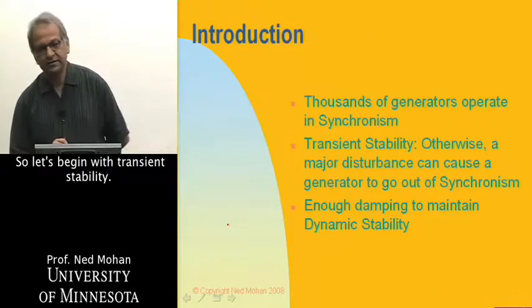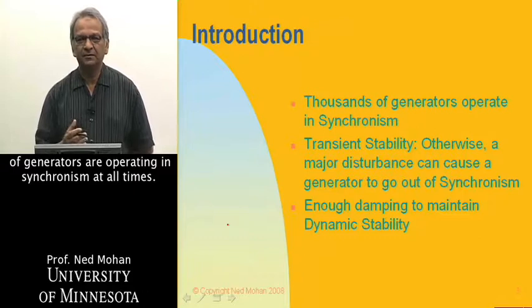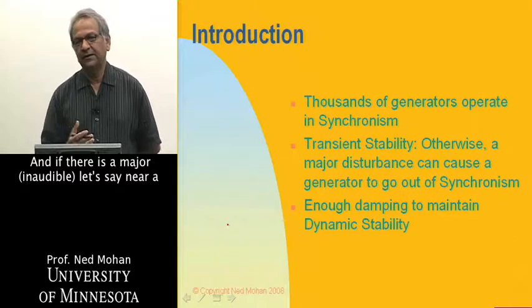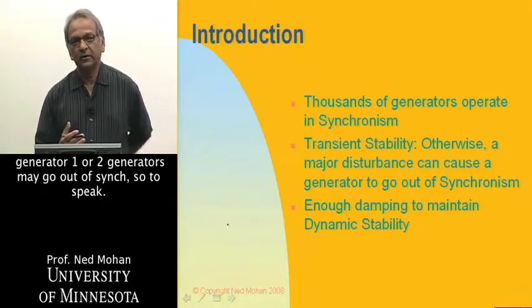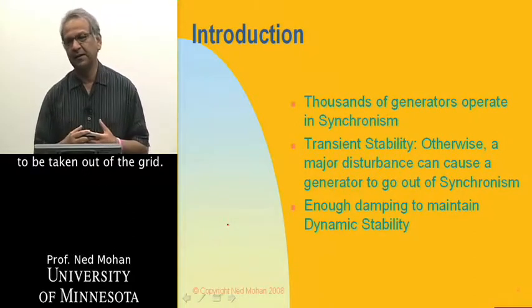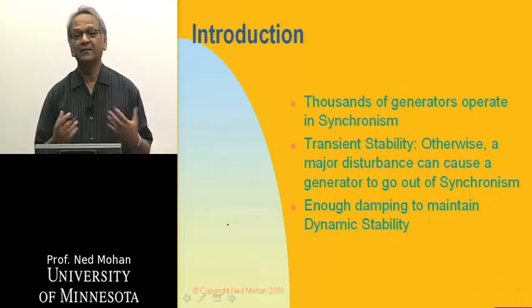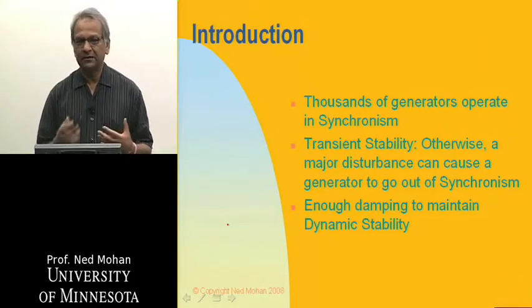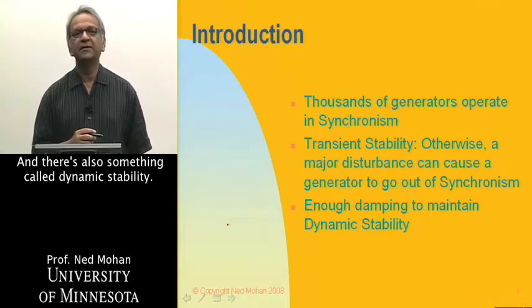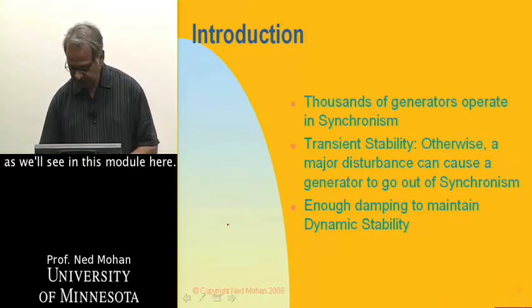In any interconnected power system, thousands of generators are operating in synchronism at all times. If there is a major fault near a generator, one or two generators may go out of synchronism and will have to be taken out of the grid. Transient stability means they do not have to be taken out, and utilities have to be constantly watching for that. There's also dynamic stability — if there's not enough damping, the system can go unstable.